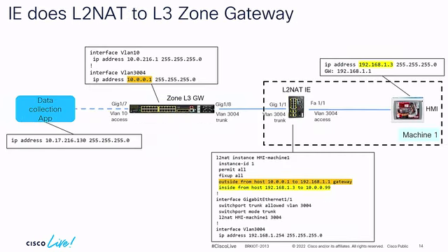All right, so this is now a different way of looking at it. We've got our HMI device over on the right. We have our layer 2 NAT switch. And below that is the configuration that we're going to use. One of the things we do with the translation is we define this layer 2 NAT instance, HMI machine 1. And we're going to show permit all and fix up all. We'll get into what those mean in a second. But most critically, the HMI machine needs to find its gateway. So if I'm going to communicate with that collection device that's in a different subnet, I need to have a gateway. It will already have been configured typically with the .1 of its subnet. And it needs to find that.